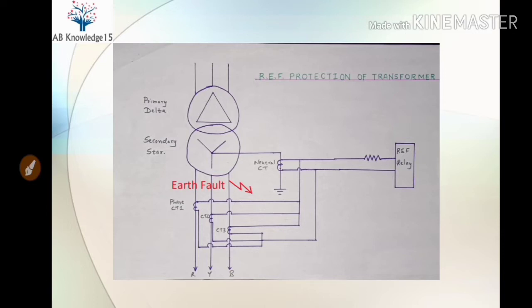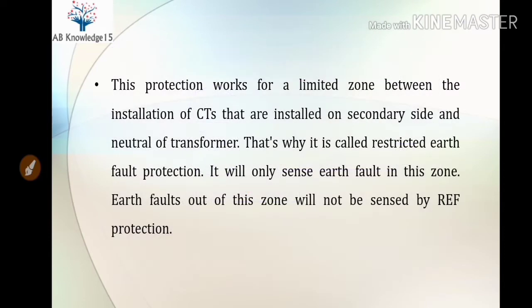The scheme of REF protection is shown here, and the earth fault that it senses is shown by the red arrow between the neutral and the secondary side of the transformer up to the secondary side panel. If any earth fault occurs between the neutral side and secondary side of the transformer, REF protection senses the earth fault and trips the circuit breaker, isolating the transformer. This protection works for a limited zone between the CTs installed on the secondary side and the neutral of the transformer.